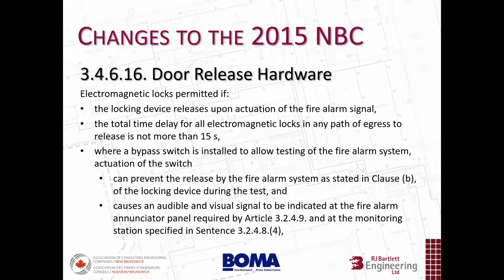Where a bypass switch is installed to allow testing of the fire alarm system, activation of the switch can prevent the release of the locking device during the test, as stated in clause B. This is that factor I was talking to you about, being permitted to override the release of these devices during testing. But it has to cause an audible and visual signal to be indicated at the fire alarm annunciator panel required by Article 3249 and at the monitoring station specified.